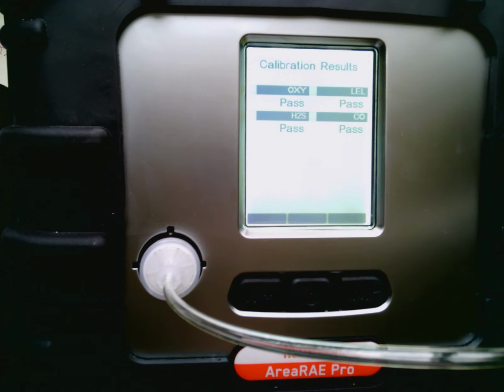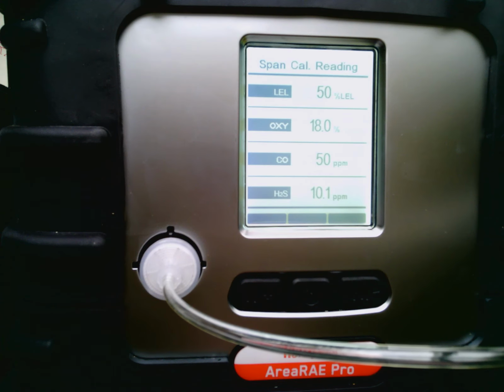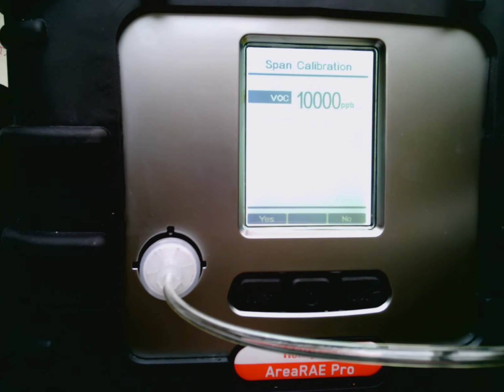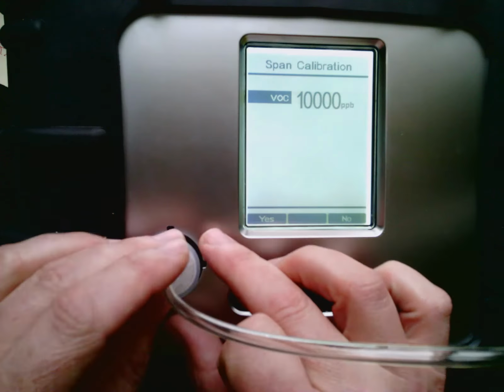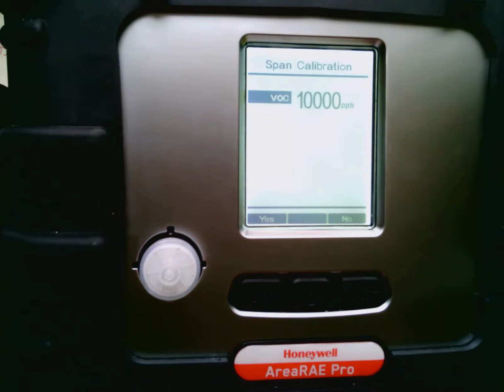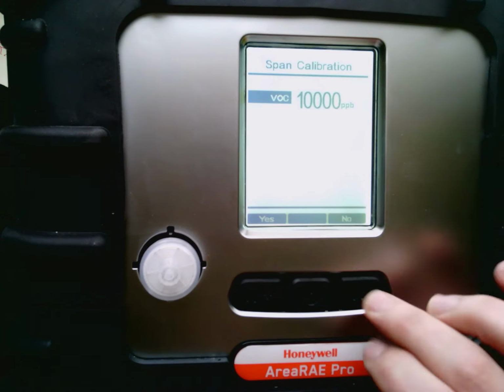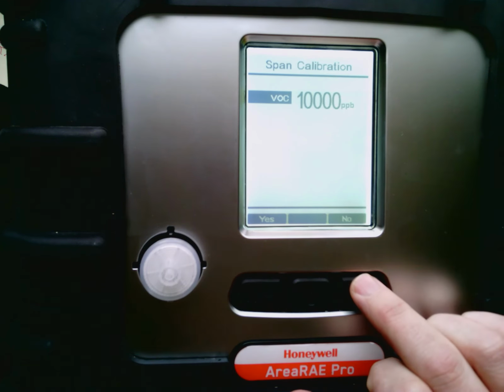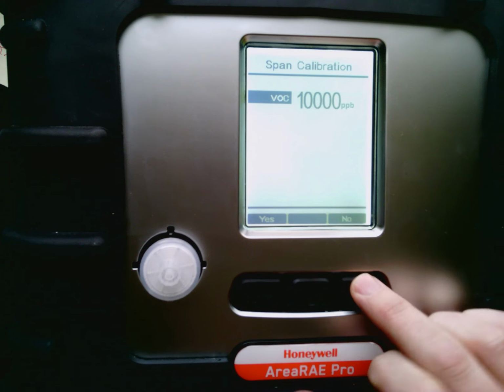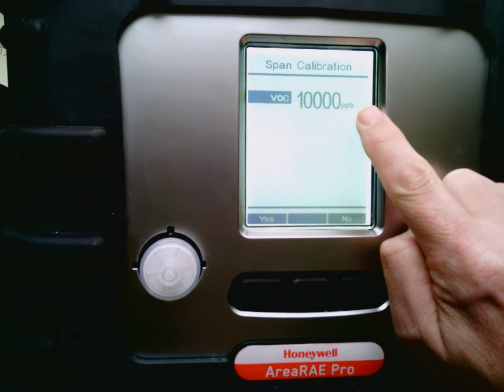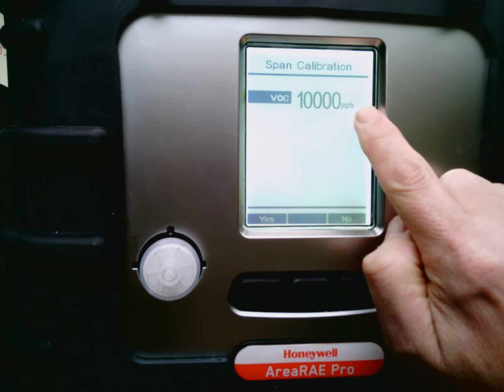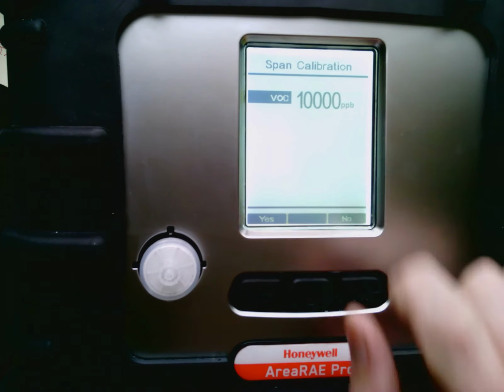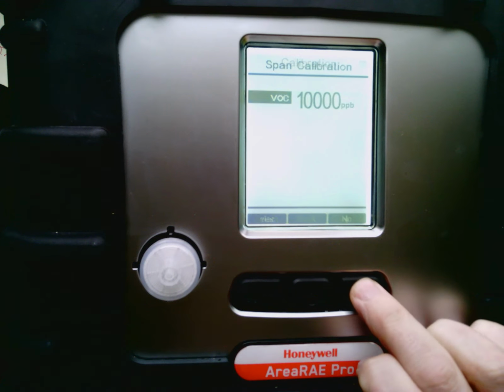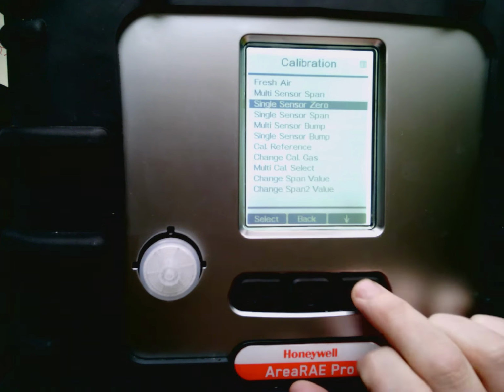All right, you notice that everything went ahead and passed. It's going to give you a snapshot of exactly what it's reading as well, and what it accepted. And then it should bounce over to the next portion of calibration. I'm going to take this gas off. For this, obviously, I don't want to calibrate to 10 ppm. Notice this is a ppb measurement. So if we move our decimals over a few, you'll see that that's 10. So I'm going to hit no, and it's going to put me back into the main menu.